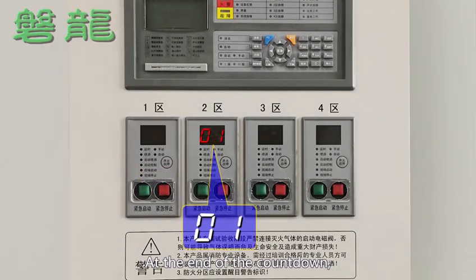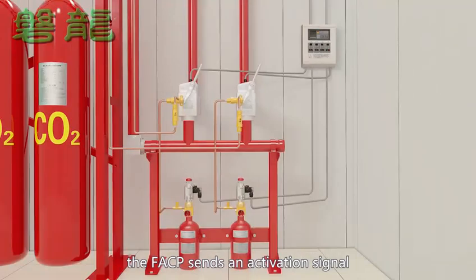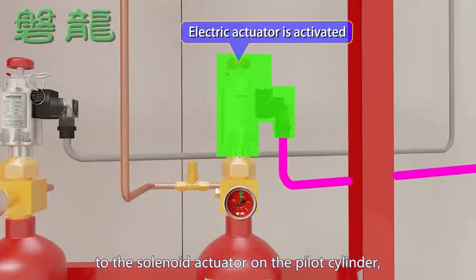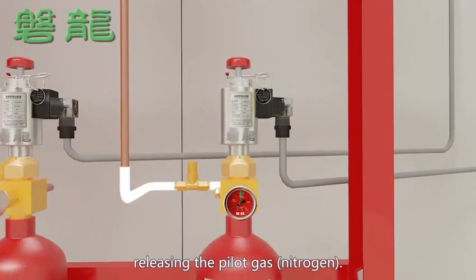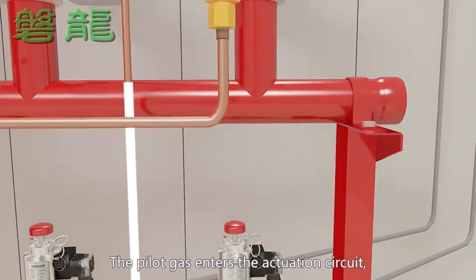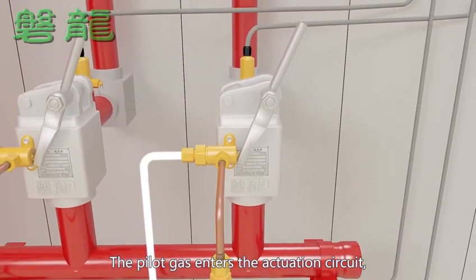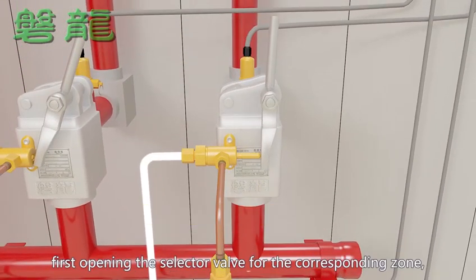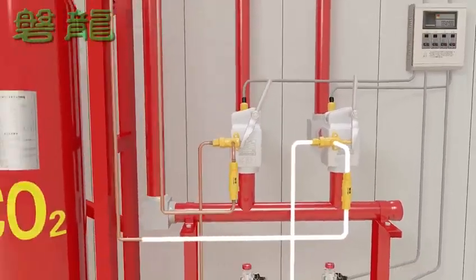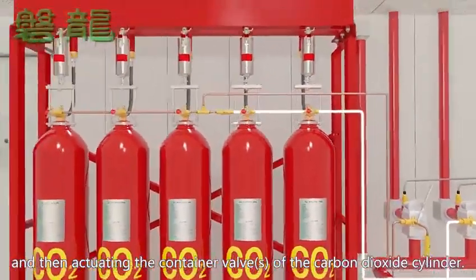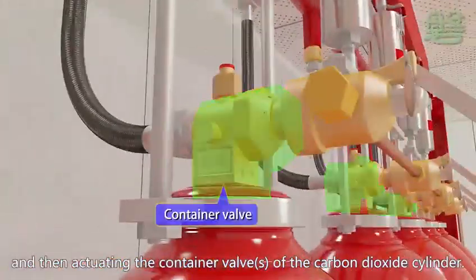At the end of the countdown, the FACP sends an activation signal to the solenoid actuator on the pilot cylinder, releasing the pilot gas. The pilot gas enters the actuation circuit, first opening the selector valve for the corresponding zone, and then actuating the container valve of the carbon dioxide cylinder.